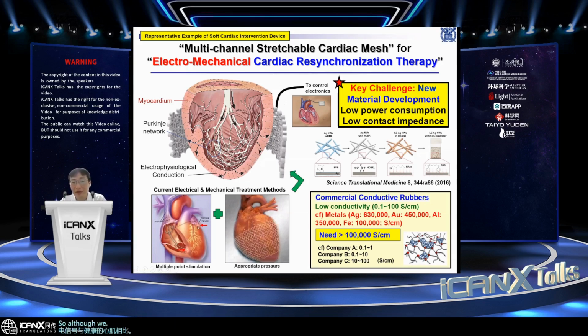So although we stimulate these 2 points, the stimulation signal cannot spread through the entire epicardium due to the dead cardiomyocytes. The solution is to use multiple electrodes to stimulate multiple points in a programmed manner, but that is not possible because we cannot insert multiple tens of electrodes through this narrow blood vessel, and also these electrodes should pass through the cardiac valve. And if many electrodes pass through the cardiac valve, then the cardiac valve will not close, so there can be another side effect. So by using a conventional implantable device, this multi-point, multi-channel pacing cannot be achieved.